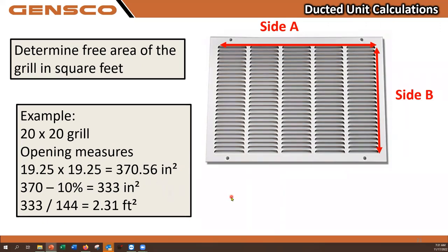That equals 370 square inches. But the actual free area of that grill is going to be that less all these louvers, which take up about 10% of that area. So my 370 minus 10% leaves me with 333 square inches. I'm going to divide that by a square foot, which is 144 square inches, and I'm left with the number we want, 2.31 square feet. The airflow formula works in area, which is in square feet, times velocity, which is feet per minute.